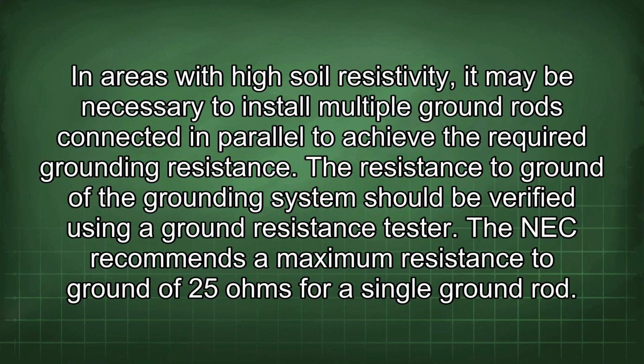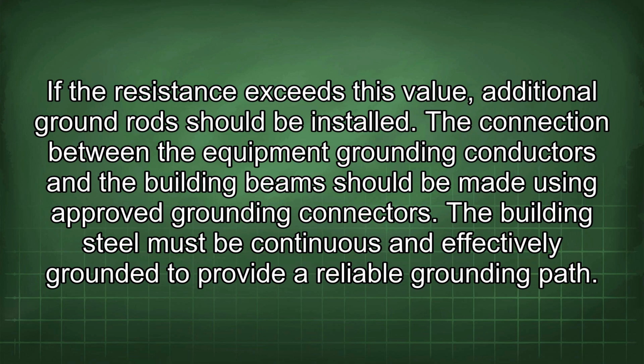In areas with high soil resistivity, it may be necessary to install multiple ground rods connected in parallel to achieve the required grounding resistance. The resistance to ground of the grounding system should be verified using a ground resistance tester. The NEC recommends a maximum resistance to ground of 25 ohms for a single ground rod. If the resistance exceeds this value, additional ground rods should be installed. The connection between the equipment grounding conductors and the building beams should be made using approved grounding connectors. The building steel must be continuous and effectively grounded to provide a reliable grounding path.